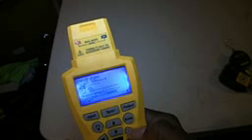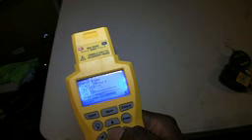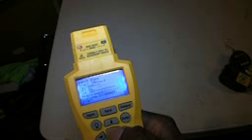Okay, and once you've got that, you want to tell it how often you want it to check. That's where the per comes into play. Just like with the span, you set your parameters, and again, you've got seconds, minutes, and hours. So in this case, we'll say for 30 hours, which is the length of the test, every 5 minutes you check the system as a whole, see what it's doing, and it'll record it for you. Then you can give it an ID and the like.